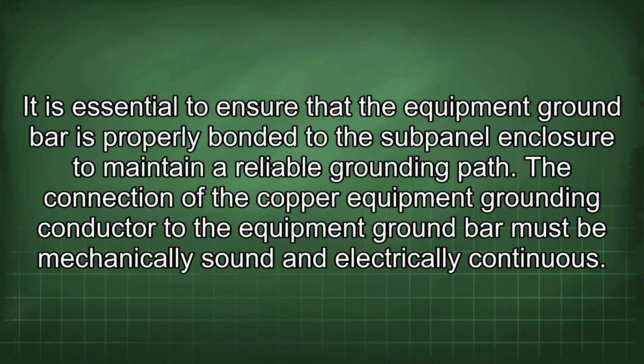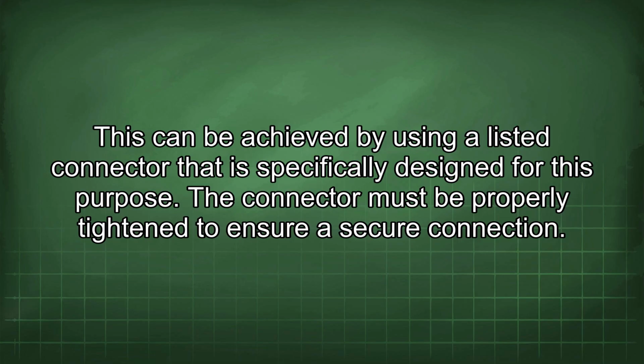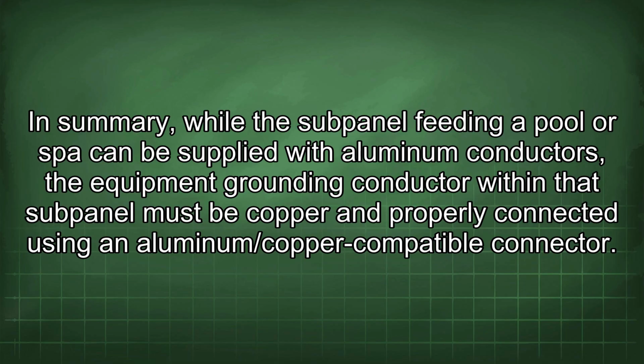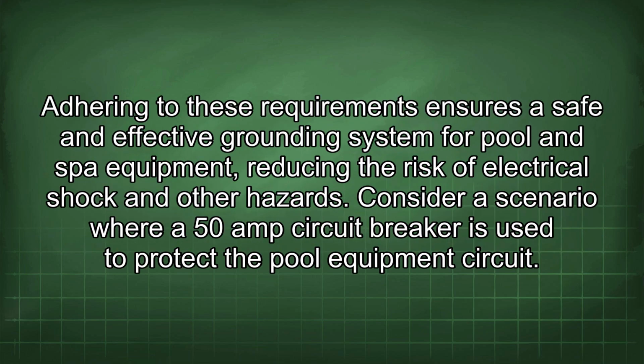a reliable grounding path. The connection of the copper equipment grounding conductor to the equipment ground bar must be mechanically sound and electrically continuous. This can be achieved by using a listed connector that is specifically designed for this purpose. The connector must be properly tightened to ensure a secure connection. In summary, while the subpanel feeding a pool or spa can be supplied with aluminum conductors, the equipment grounding conductor within that subpanel must be copper and properly connected using an aluminum/copper compatible connector. Adhering to these requirements ensures a safe and effective grounding system for pool and spa equipment, reducing the risk of electrical shock and other hazards.